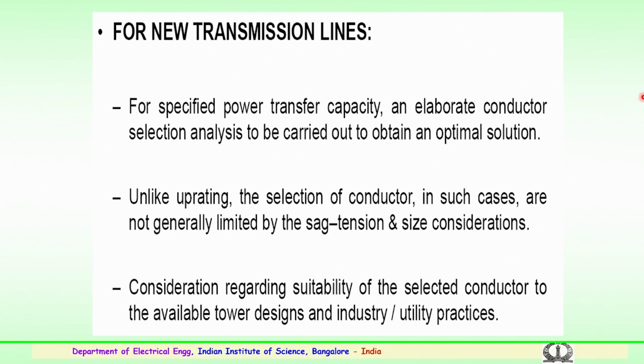So, when going in for new transmission lines for a specified power transfer capability, an elaborate conductor selection analysis is to be carried out to obtain an optimal solution. Unlike the upgrading or uprating of conductors, here the selection of conductor is not generally limited by sag and tension considerations.